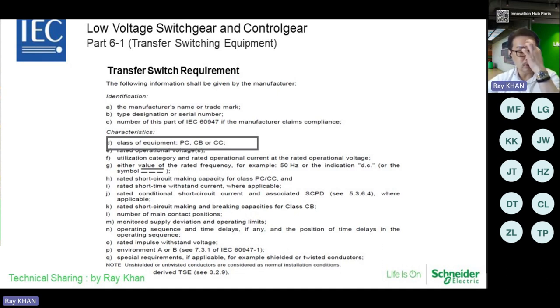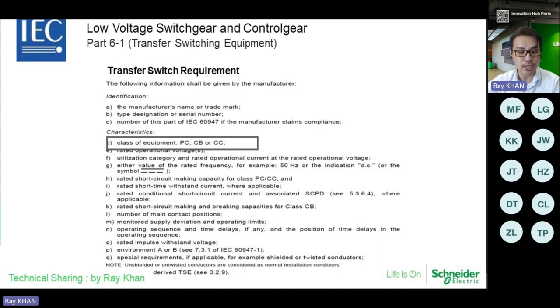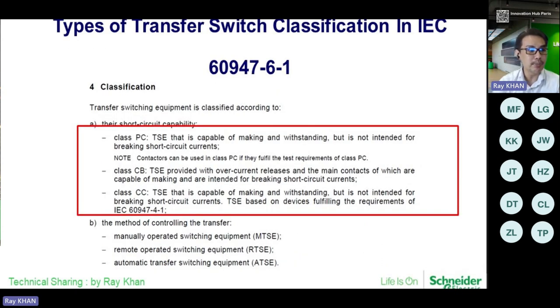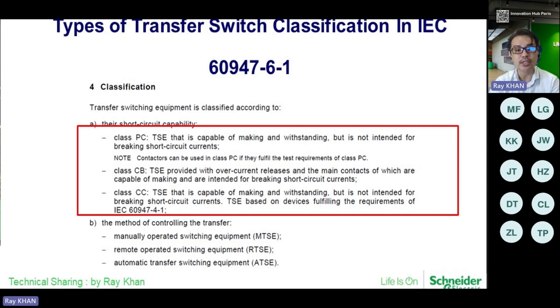Next, the transfer switch class requirement. There are three types: PC, CB, and CC, as indicated in IEC 60947-6-1. Designers must decide on the class of transfer switch. Class PC is TSE capable of making and withstanding, but not intended for breaking short-circuit current — a transfer switch designed and manufactured by ATS manufacturers. Class CB is TSE provided with overcurrent releases, where the main contacts are capable of making and intended for breaking short-circuit current. Class CC is capable of making and withstanding but not intended for breaking short-circuit current, and is based on devices fulfilling IEC 60947-4-1.